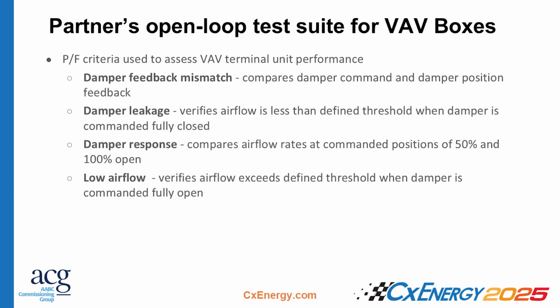And then out of those 45 units, they had 14 instances of failed tests among the systems that they tested. So the pass-fail criteria in this case is, for instance, if you're modulating the damper, you're going to look to see whether or not there's a mismatch between the damper position and the command, right? So if you commanded the damper to 100%, but the position stays at 50, then there's something going on, right? And you're going to flag that as a failed test.